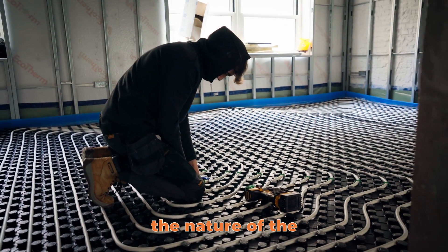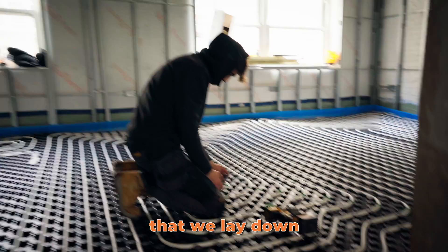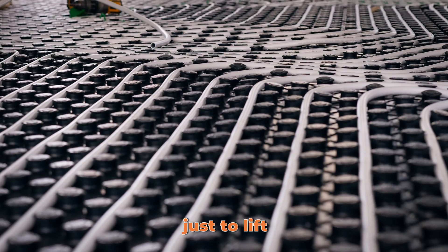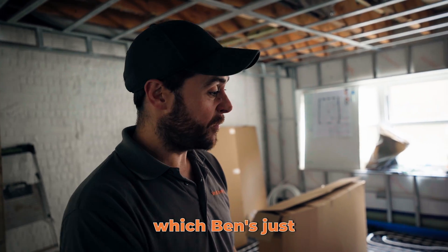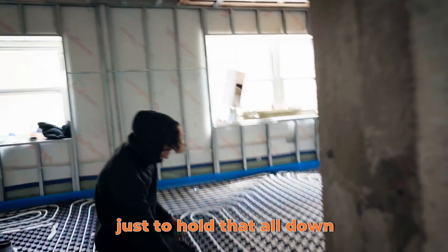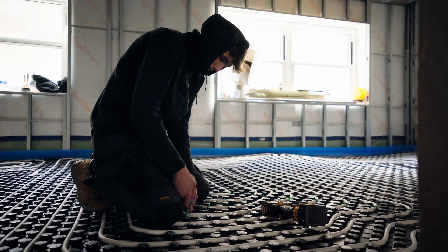Ben is just providing some additional clipping here. The egg crate style tray that we lay down helps us route the pipe, but just under the tension of the pipework it has a tendency to lift. So we've got Celotex-style insulation underneath the crate, and Ben's putting some additional clips to hold that all down so that when the screed goes down we've got no high points in the floor at all.